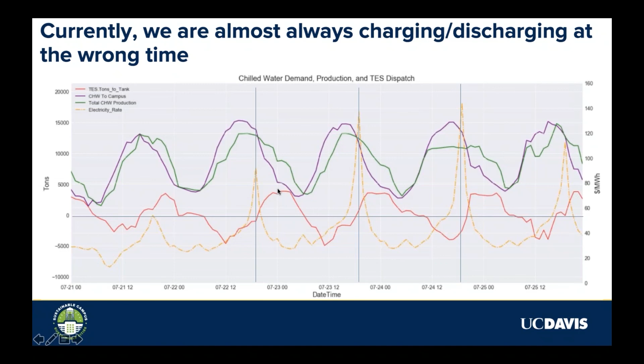So, an optimization program developed by a chemical engineering grad student, Gustavo Campos. He wrote a mixed integer linear program that takes in our chilled water demand forecast, our day-ahead market rate, and then the outside air wet bulb temperature forecast, and then makes decisions on how many chillers and which chillers should be on and off, and how much of that production should go to the tank or come out of the tank.